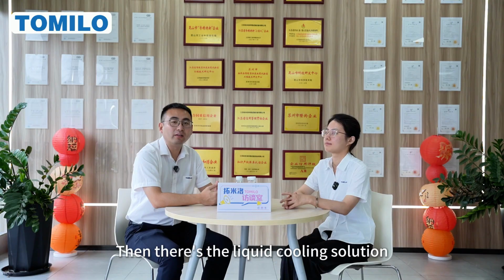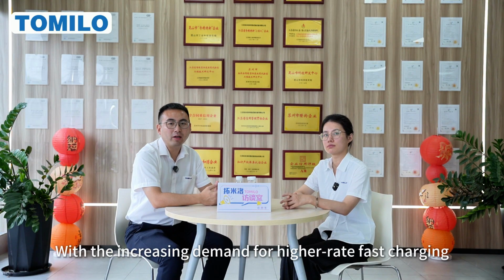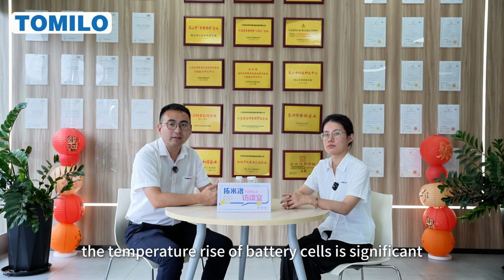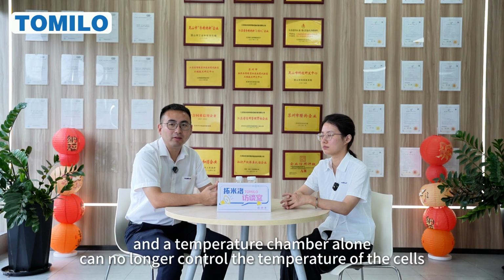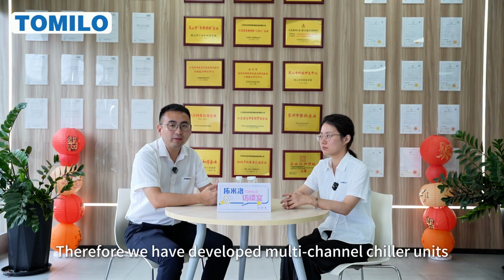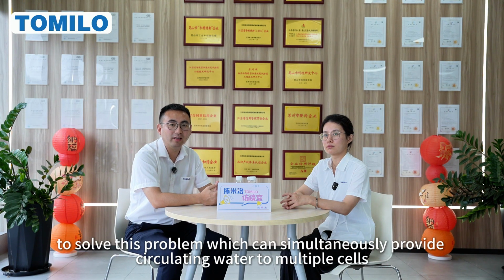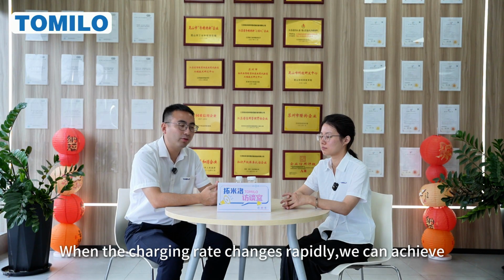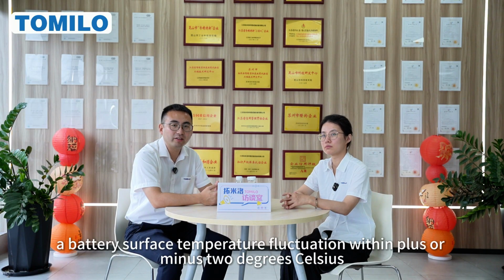Then there's the liquid cooling solution. With increasing demand for high-rate fast charging, the temperature rise of battery cells is significant, and the temperature chamber alone can no longer control cell temperature. So we developed multi-channel chiller units to solve this, which can simultaneously provide circulating water to multiple cells. When the charging rate changes rapidly, we can achieve a battery surface temperature fluctuation within plus or minus 2 degrees Celsius.